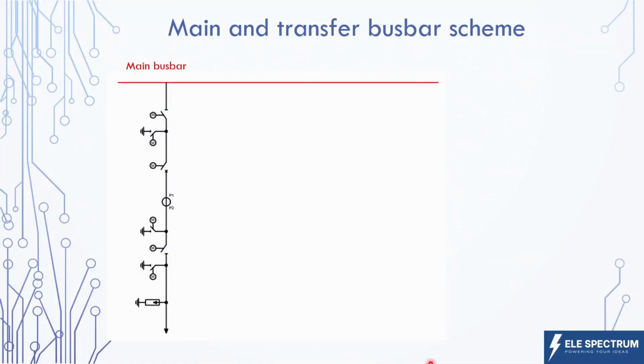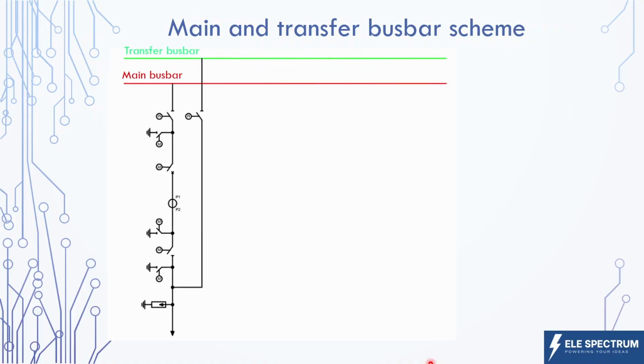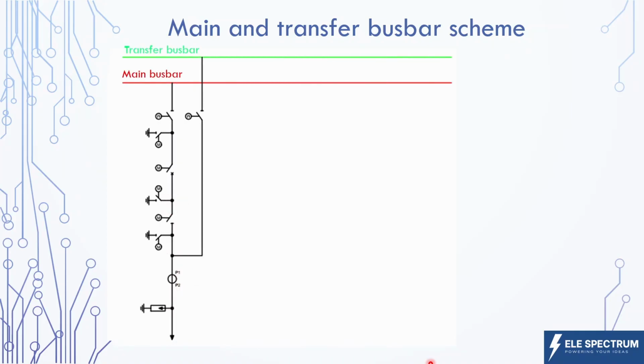So for this purpose, we need to take a tap just after the surge arrestor and connect it to the transfer bus bar through a disconnector. Here, for this arrangement, we also need to relocate the CT just after the surge arrestor. So suppose power is flowing through the usual path, then we are able to measure the current. And in case we are diverting it to the transfer bus bar, in that case also we are able to measure the current. If we are choosing this path of the transfer bus bar, then we also need to connect this power again to the main bus bar.